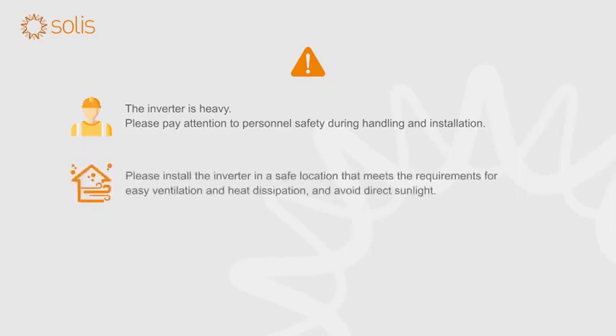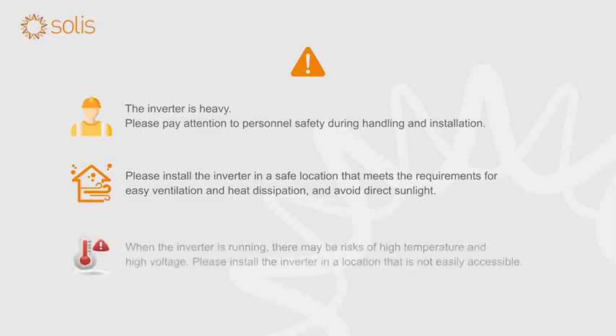Please install the inverter in a safe location that meets the requirements for easy ventilation and heat dissipation. When the inverter is running, there may be risks of high temperature and high voltage. Please install the inverter in a location that is not easily accessible, and avoid direct sunlight.